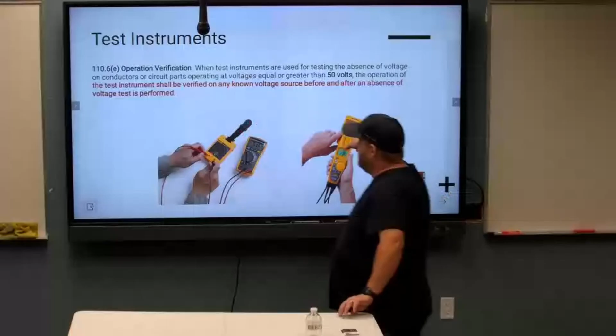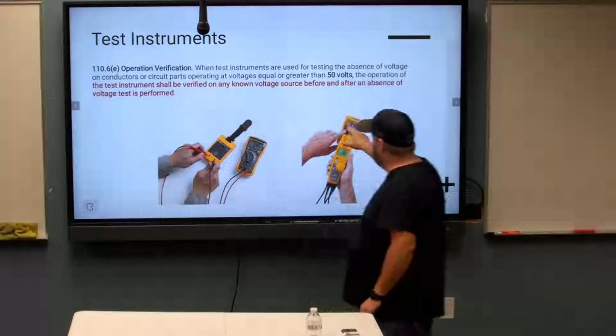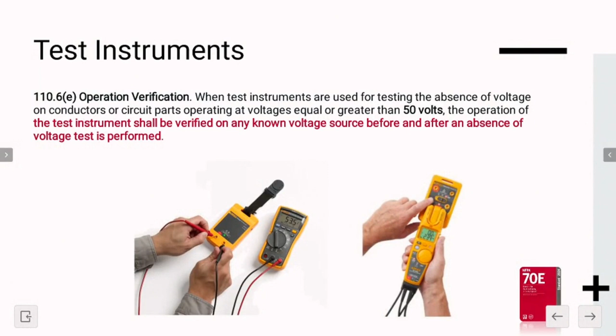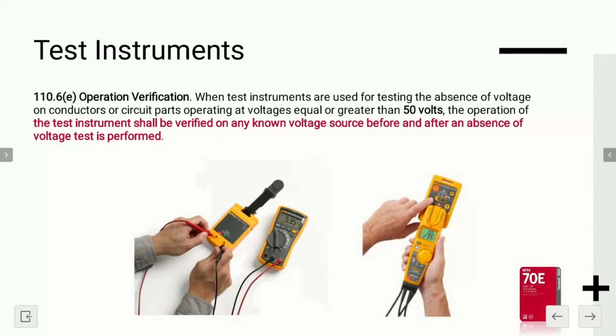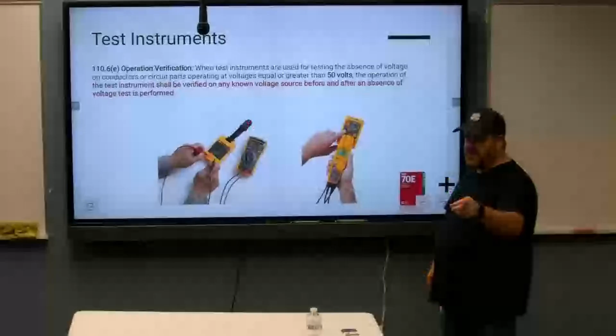Now, Fluke has a cool thing out. I just really like it. I don't get endorsed or paid by Fluke. I wish I did, but I don't. It's called the Fluke Proving Unit. This is your known energy source right here. You can hang it up at your work area. You can test your meter, do your absence of voltage test, then test it again on the proving unit. Now you know your meter's working correctly. And they make them for different types of testers, for amp readers, meters, probes for meters, things like that. And that also includes your induction tester, or idiot stick. You brought that up a little earlier.